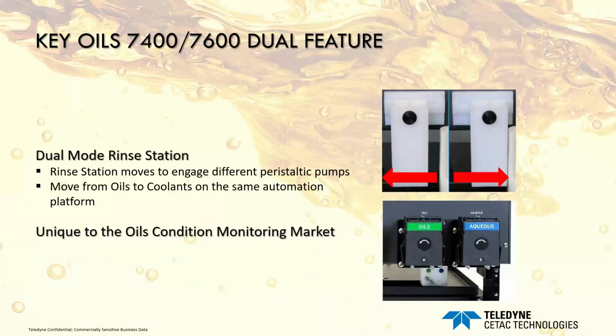And last but not least, we have the ability to easily switch between oil and coolant samples. And we achieve this by including 2 separate peristaltic pumps, a dual position rinse station mount and a dual channel rinse station. The rinse station has 2 completely separate fluid paths, including tubing connectors. And you can see in the image that on the lower one that we've got metal connectors on the oil side and non-metallic connectors for the aqueous or coolant side.